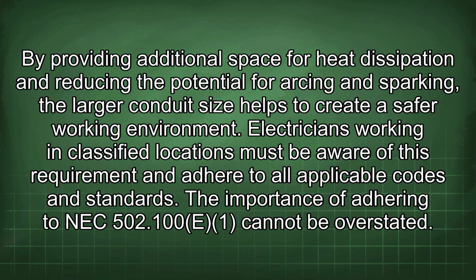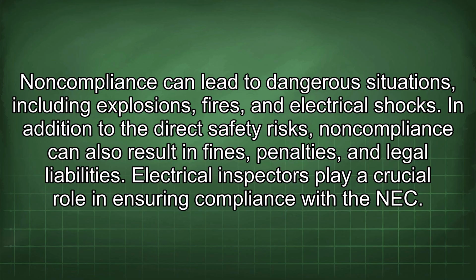By providing additional space for heat dissipation and reducing the potential for arcing and sparking, a larger conduit size helps to create a safer working environment. Electricians working in classified locations must be aware of this requirement and adhere to all applicable codes and standards. The importance of adhering to NEC 502.100 cannot be overstated. Non-compliance can lead to dangerous situations, including explosions, fires, and electrical shocks.